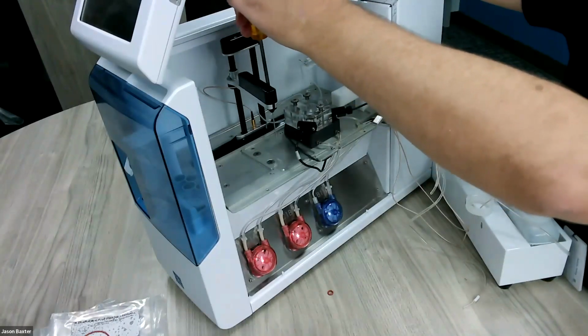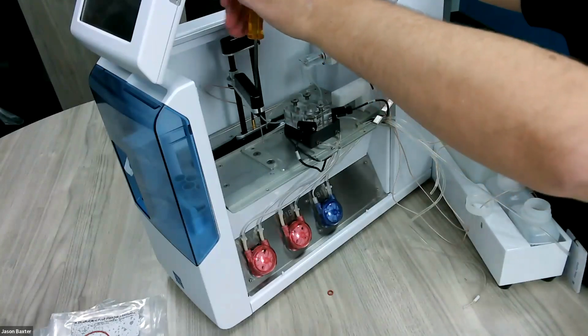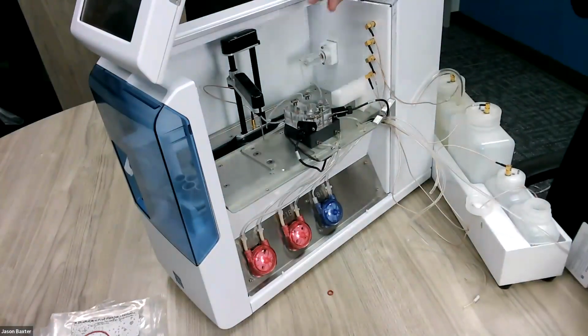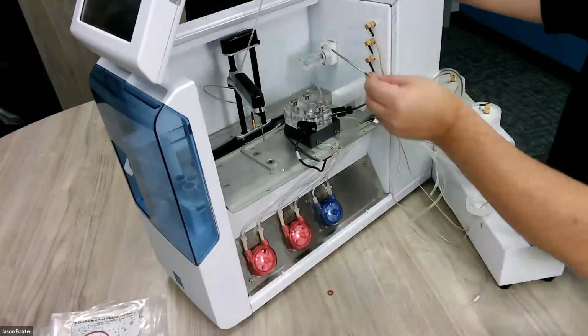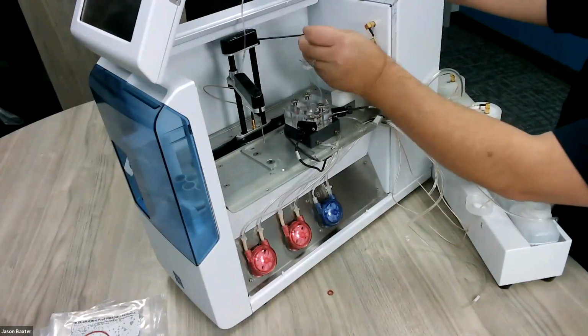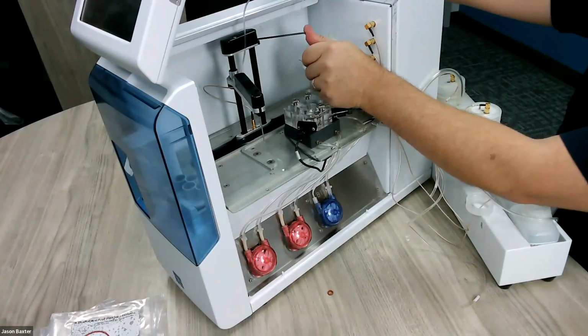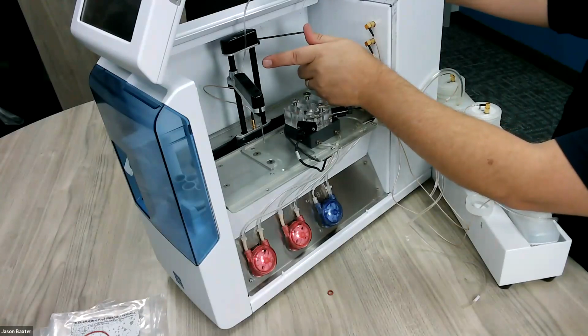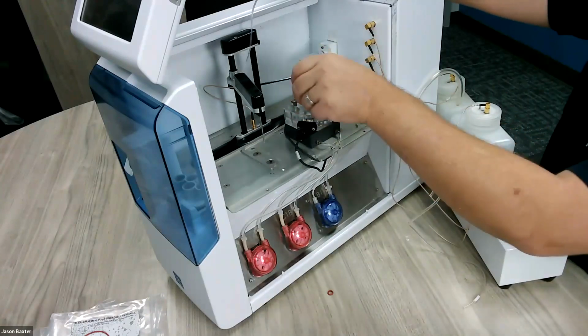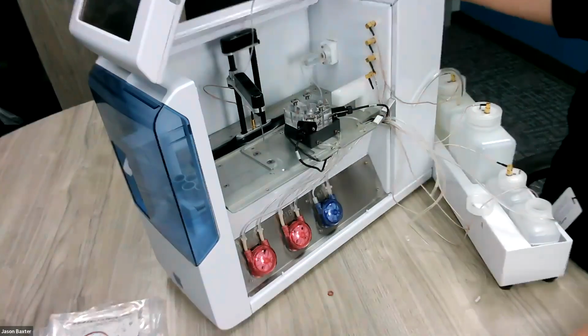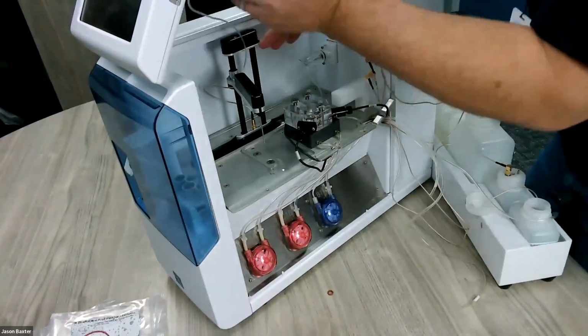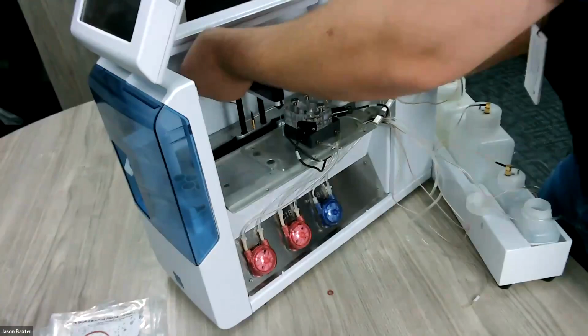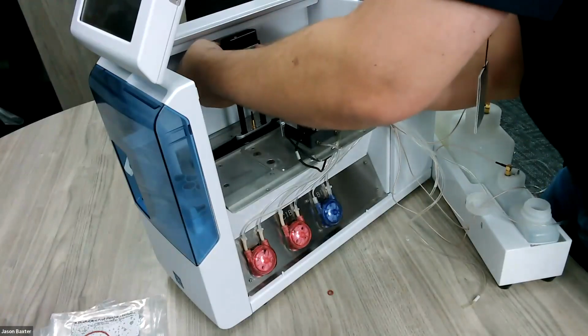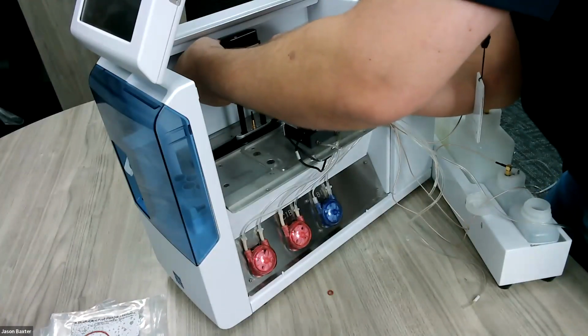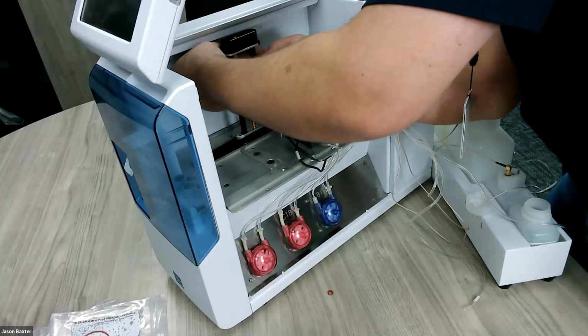And one of the last parts before we're finished, this free end of the tubing has to go through a small hole that's back here on the back of the zipper armature. If you don't route the tubing through this hole, the tubing can actually get wrapped up inside of this armature and cause all kinds of mechanical problems and error codes and things like that. So just take the extra few seconds and route it through the proper way.